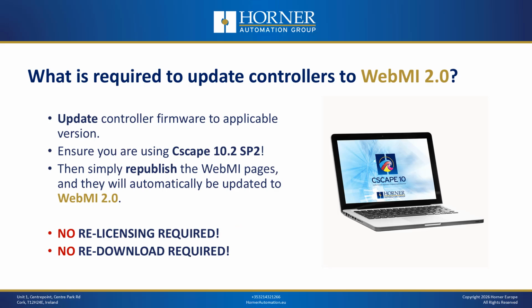What is required to upgrade controllers to WebMI 2.0? First, update your controller's firmware to a suitable version for this series that supports WebMI 2.0. We've shown suitable versions in a previous slide. Then, ensure you are using Cscape 10.2 Service Pack 2. After that, simply republish the WebMI pages and they will automatically be updated to WebMI 2.0. There is no relicensing required and no re-downloading of your program required either.